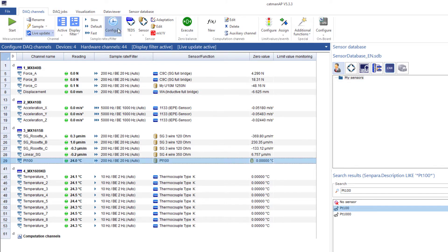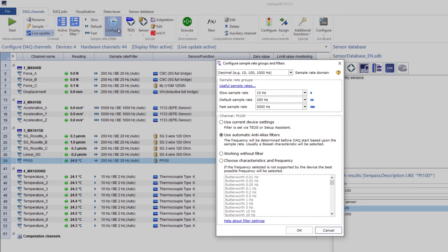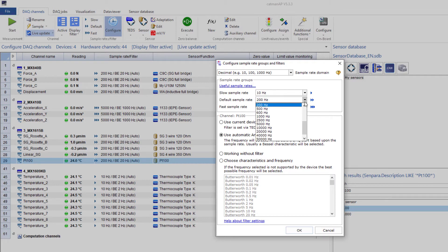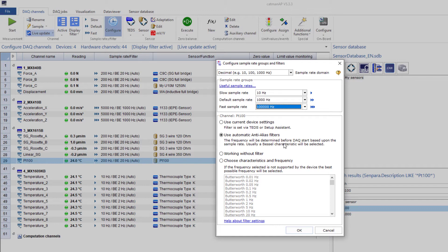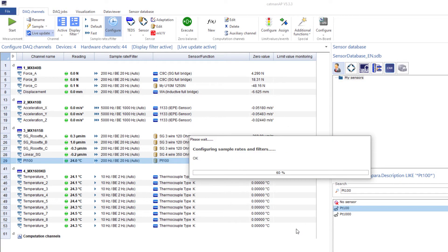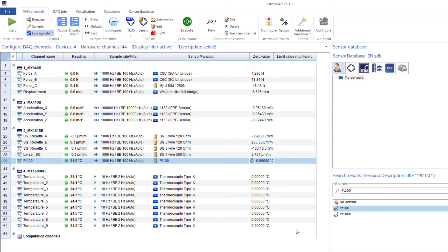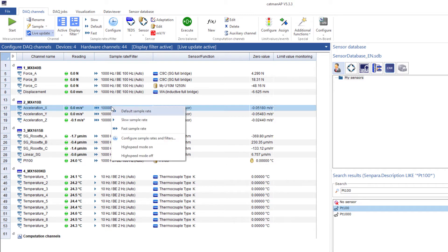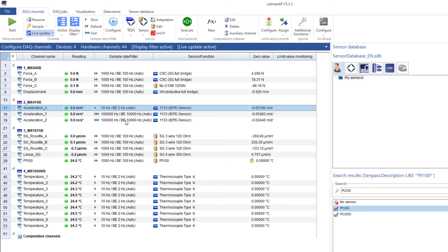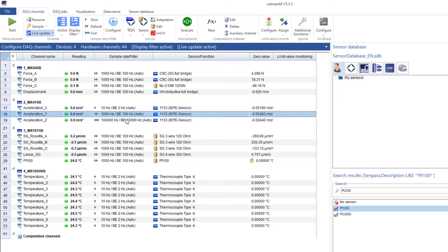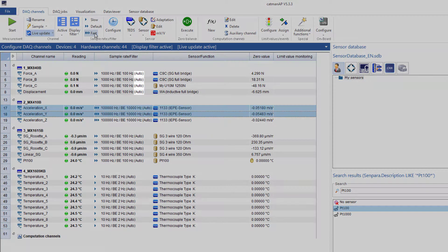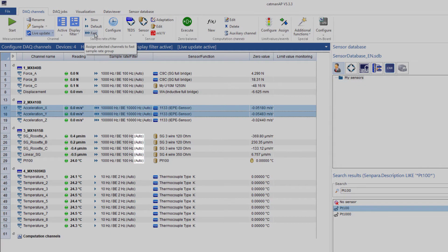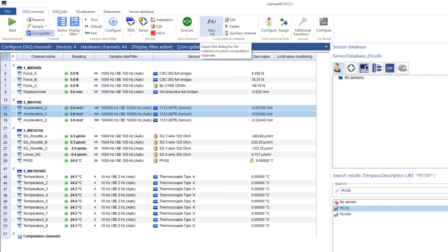I'll now define the sample rates of the individual channels. Catman supports three sample rate groups. Under Configure, I'll now select the sample rates I need. You will not always need all three sample rate groups. If possible, always use the default sample rate. Catman has already assigned the appropriate sample rate groups to the individual modules. Of course, I can also adjust the settings channel by channel if necessary. I leave the filter settings as Auto. A separate video on sample rates and filters is also available.